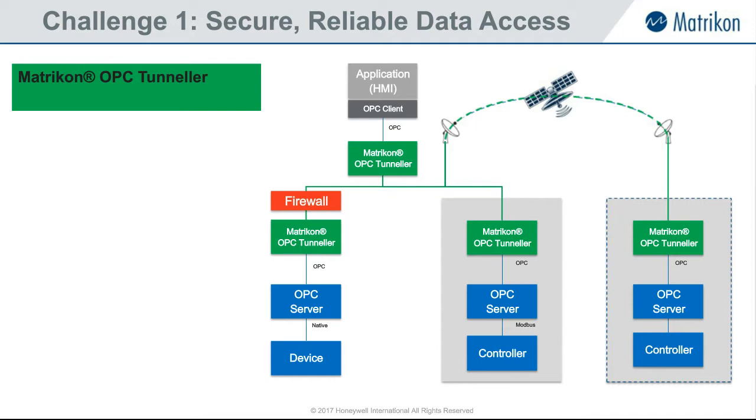So in OPC, you have a client and a server which communicate. The client is typically built into the application, so it natively knows how to communicate with all sorts of OPC servers, regardless of which vendor they come from, which is the main selling point of OPC: vendor-independent connectivity. Because basically, if you have an OPC server that is compliant with OPC specifications, then any OPC client that is also compliant with those specs is capable of talking to it and actually getting the data from it.